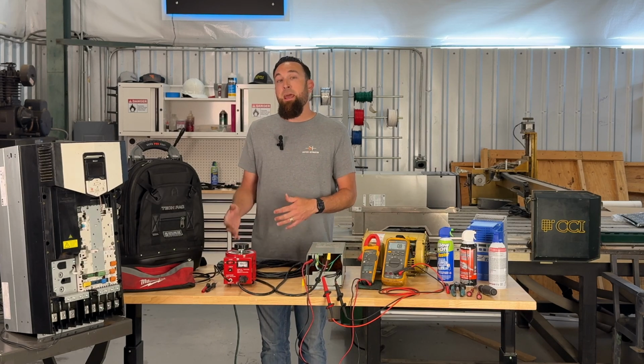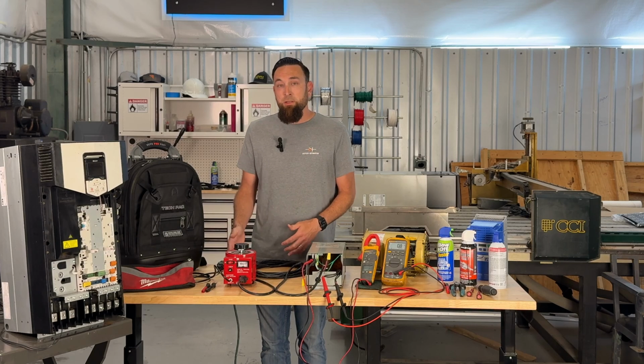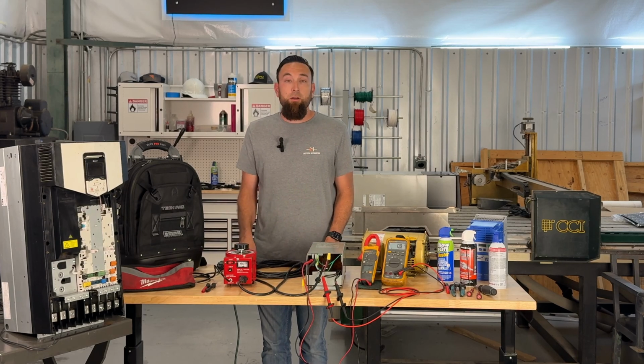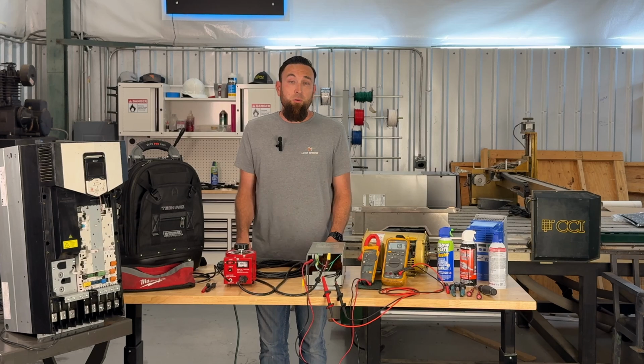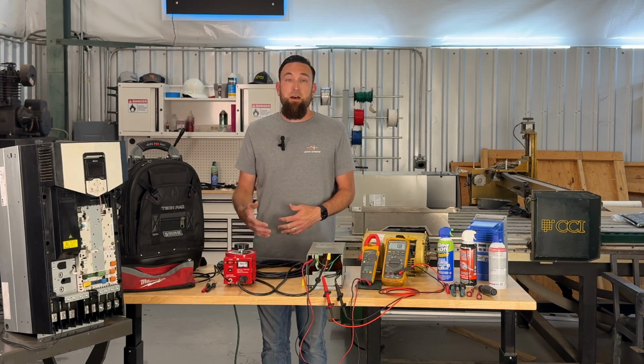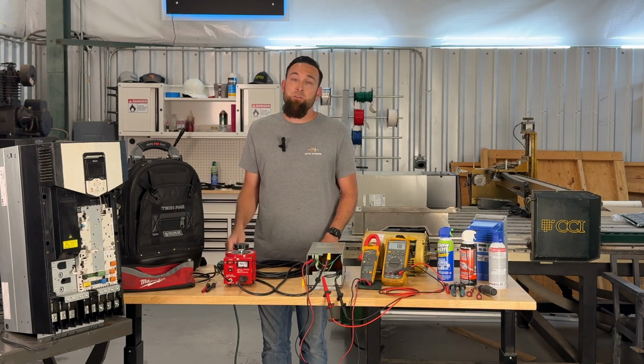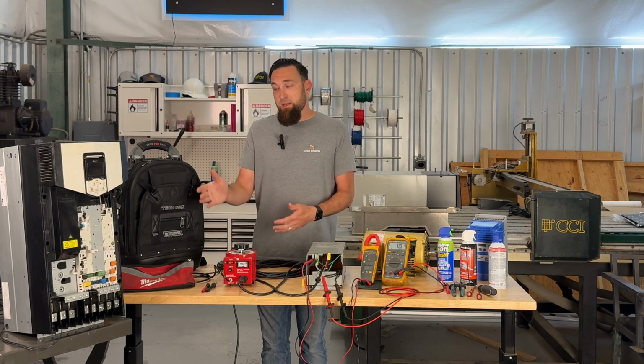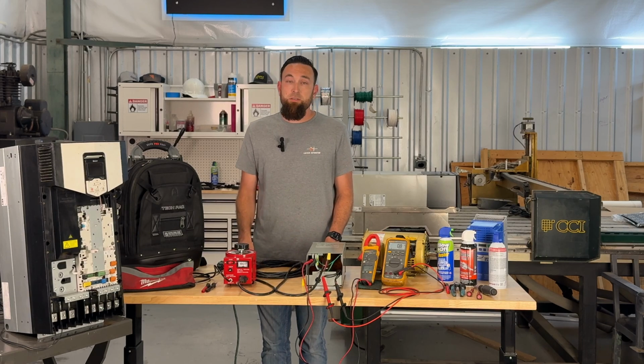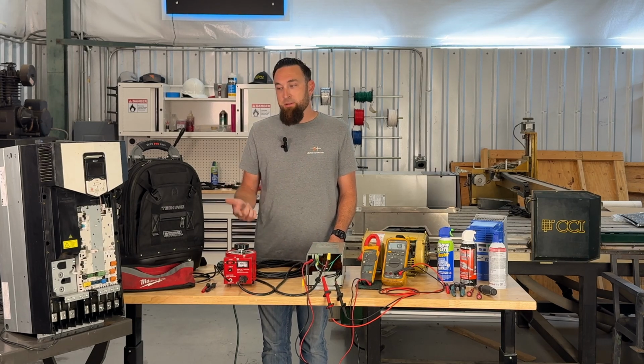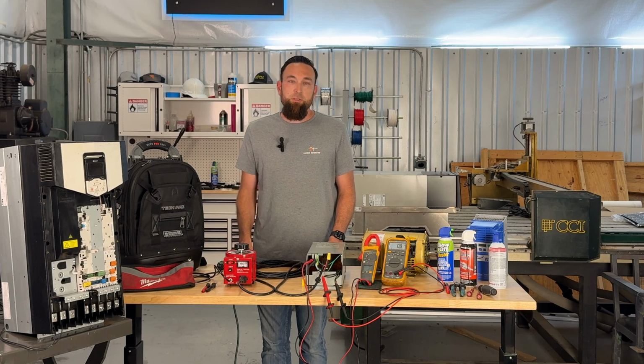Some of these drives can have new capacitors installed, but this is throwaway culture nowadays. Typically anything under about 150 horsepower is considered throwaway for most brands. The bigger 500, 1,000 horsepower modules are rebuildable, but for things of this size you're very hard pressed to be allowed to buy parts. So typically at that point you're just looking for a new drive. If it's not the fans or the control board, you're probably just going to have to get a new drive.